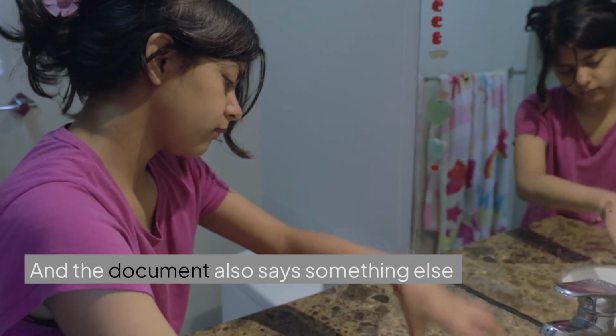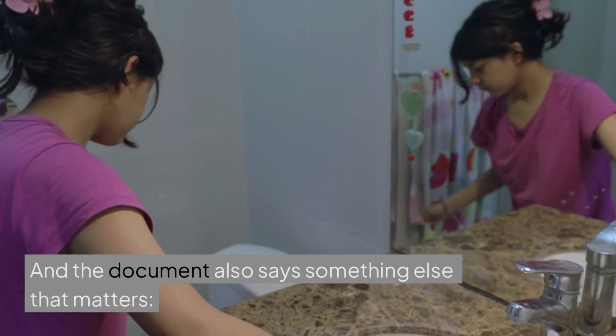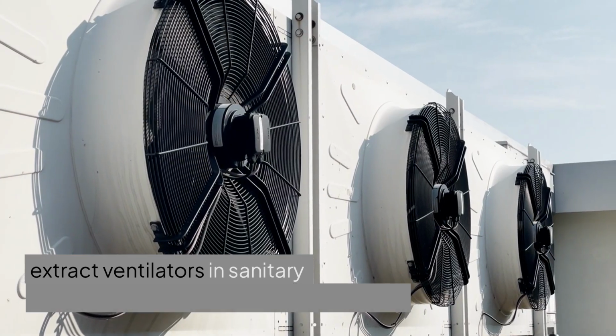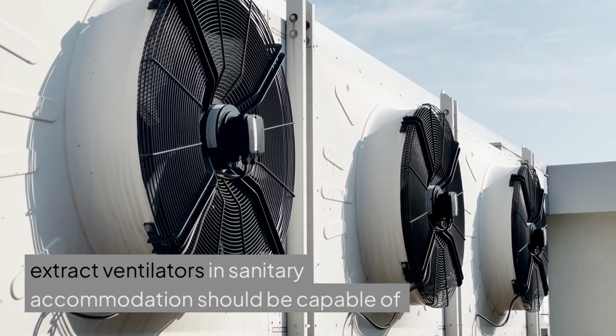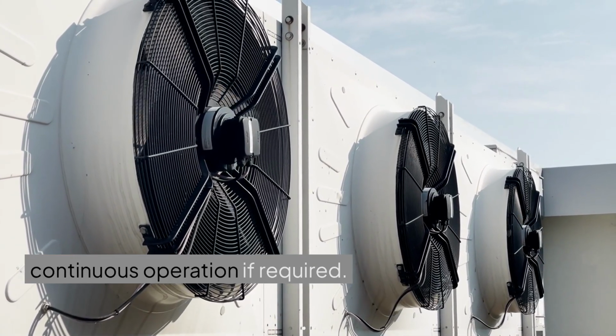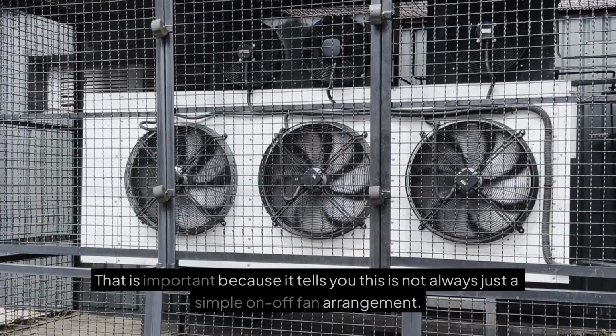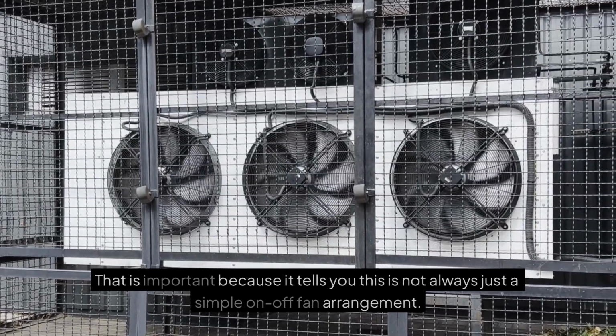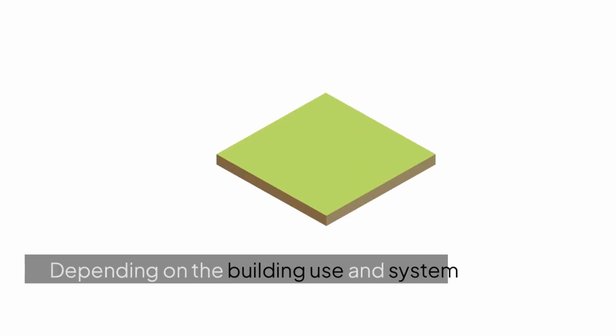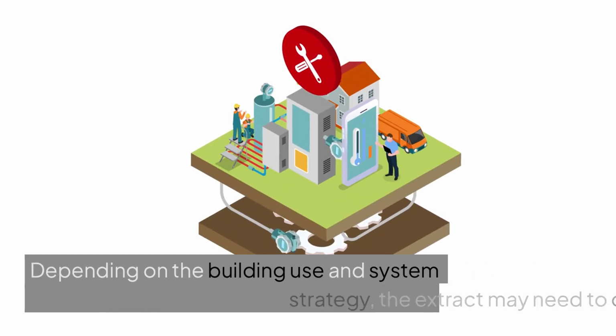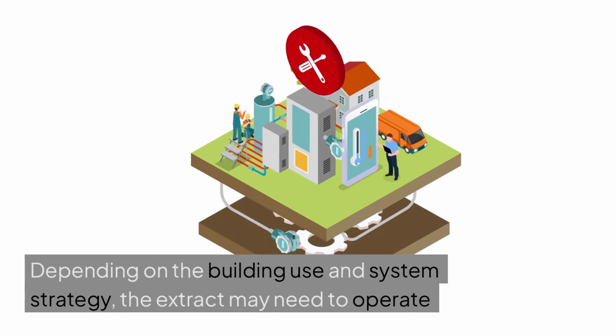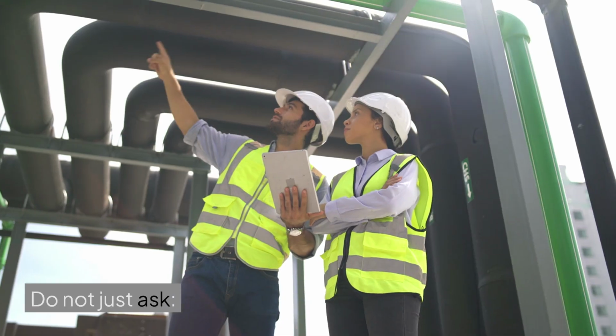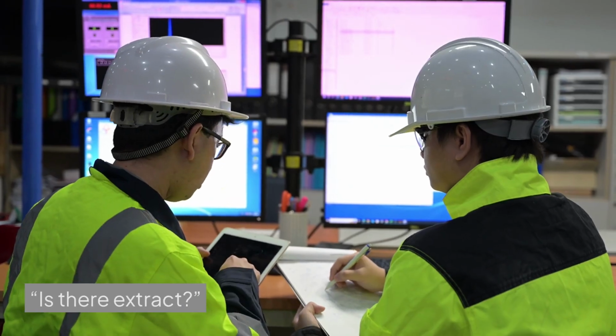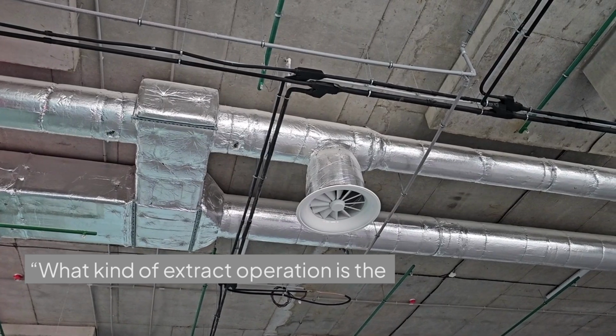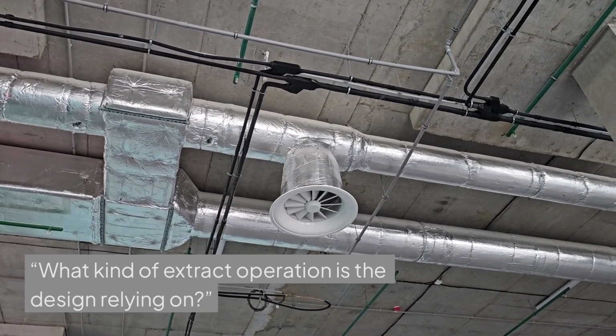And the document also says something else that matters. Extract ventilators in sanitary accommodation should be capable of continuous operation if required. That is important because it tells you this is not always just a simple on-off fan arrangement. Depending on the building use and system strategy, the extract may need to operate continuously. That is the first junior engineer watch point. Do not just ask, is there extract? Also ask, what kind of extract operation is the design relying on?